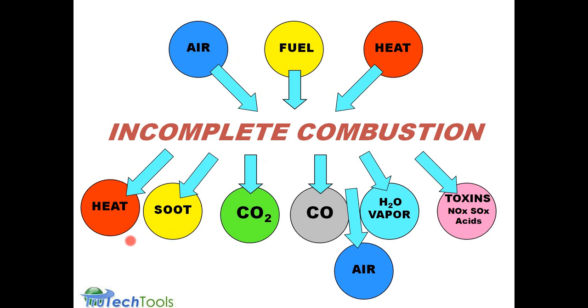It reads the temperature of the flue gas, which shows how much heat. It can read the oxygen that's left over, and from that infer how much carbon dioxide is in the flue gas. It can actually directly read carbon monoxide. And some advanced analyzers can read nitric oxide and sulfur dioxide. So the combustion analyzer works on this side in order to tell you what's happening in the combustion process back here. It's kind of like an X-ray. It allows you to see indirectly what's going on inside the process.